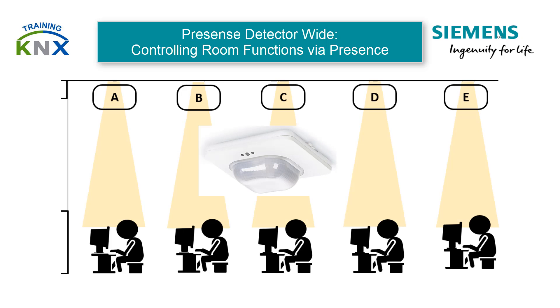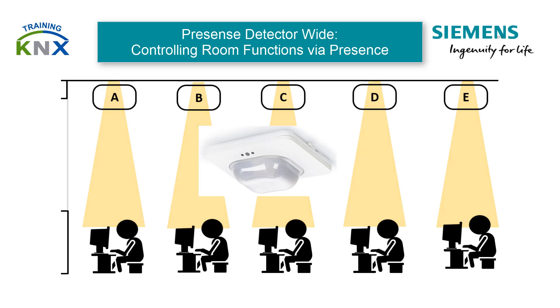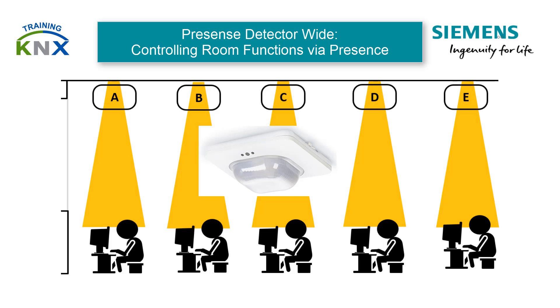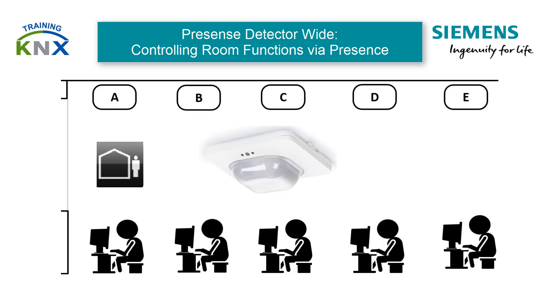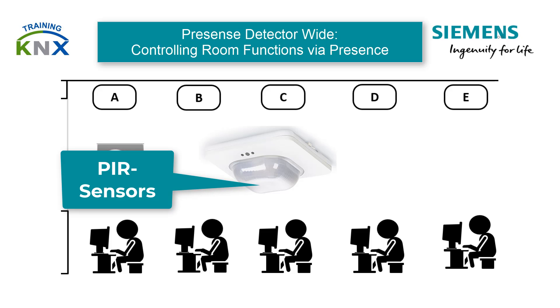Up to now, presence sensors have mostly only been used to switch lighting. However, more and more often now the control of room air conditioning is also included. The function of the presence detectors is based primarily on passive infrared sensors, which are present in all Siemens Presence Detectors Wide alike.